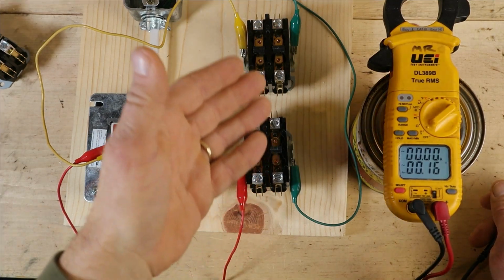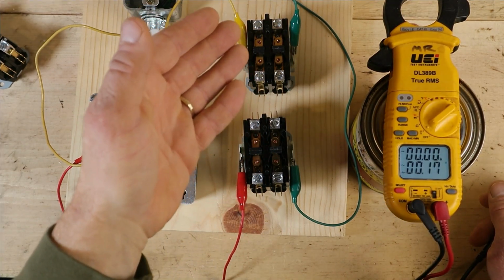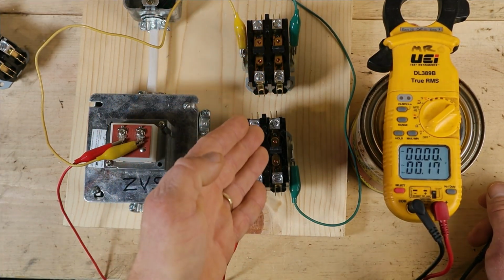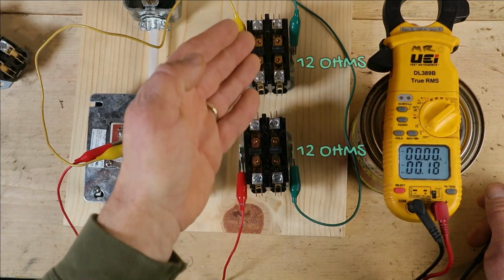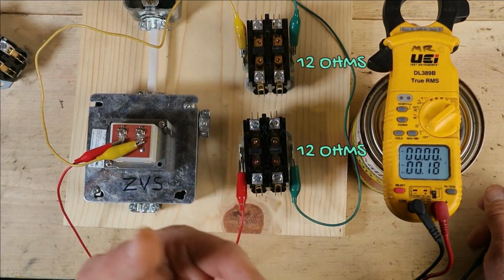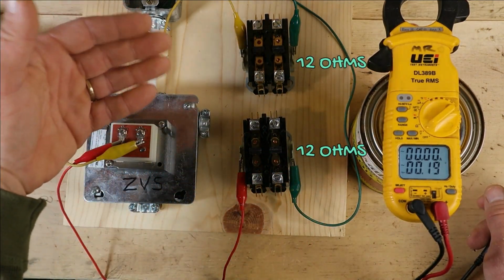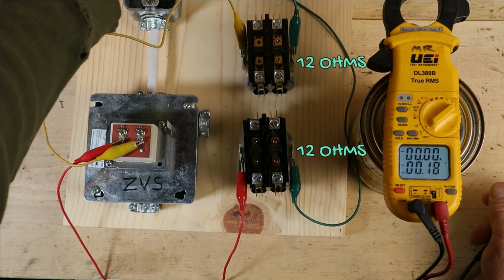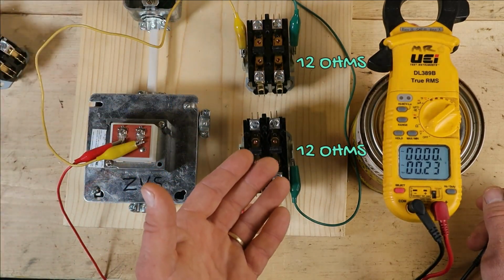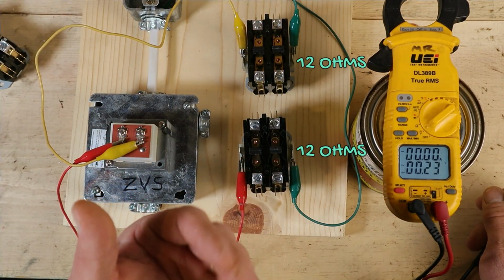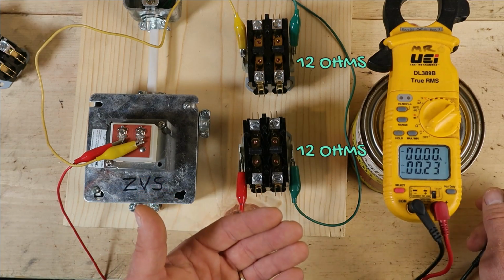Now what I have here is I removed the resistor and I put another contactor in that's identical to this one. So both of these contactors have about the same resistance reading, about 12 ohms. So let's go ahead and turn on our power, see what happens. Now you can hear they're chattering, all right? There's not enough voltage there to pull these contacts in.